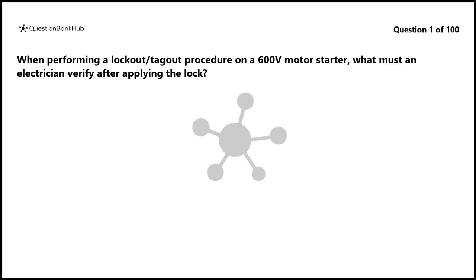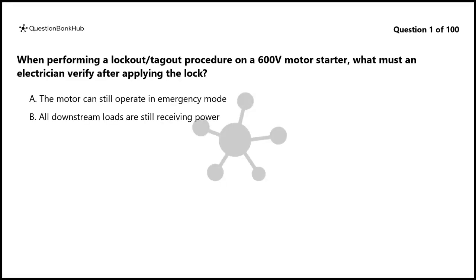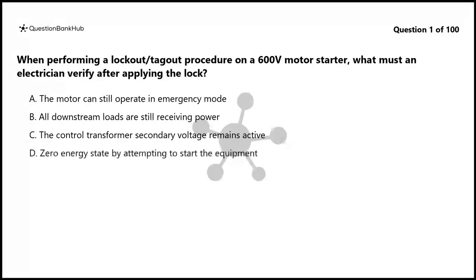Question 1. When performing a lockout/tagout procedure on a 600 volts motor starter, what must an electrician verify after applying the lock? A. The motor can still operate in emergency mode. B. All downstream loads are still receiving power. C. The control transformer secondary voltage remains active. D. Zero energy state by attempting to start the equipment.